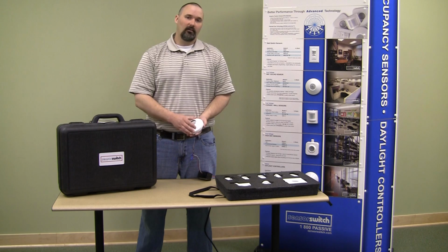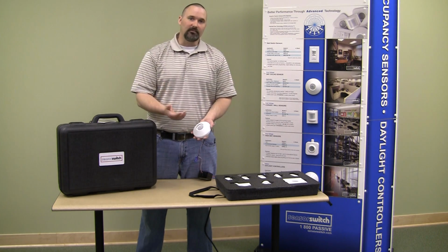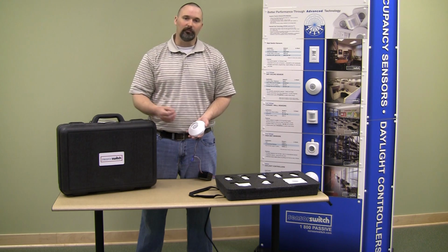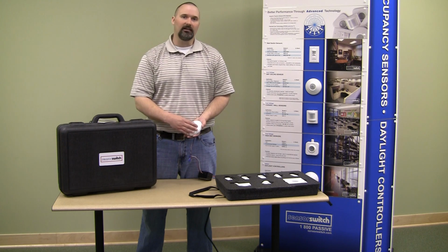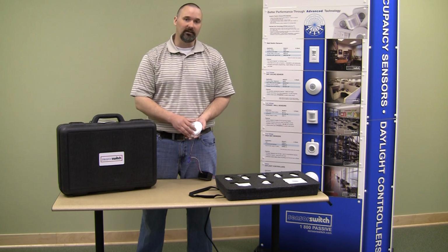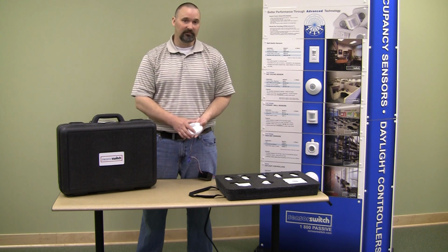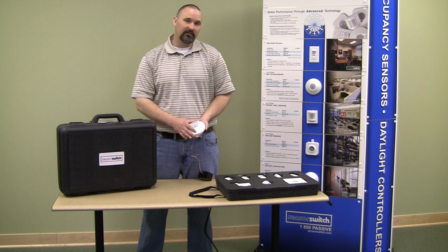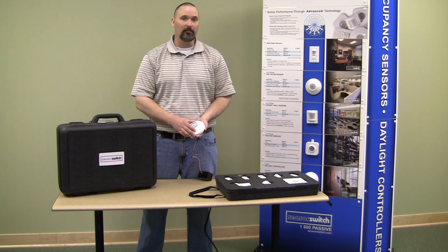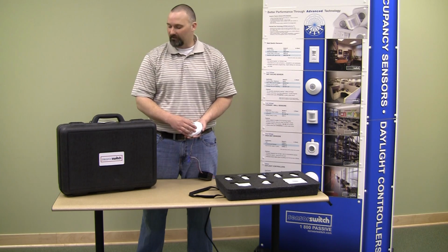space. The way that microphone operates is that first the sensor has to see you. At that point, we turn on that microphone. Once the sensor detects vacancy, meaning that it hasn't seen you or heard you for a period of 10 minutes, that occupancy sensor will turn the lights off. When those lights turn off, we keep that microphone on for an additional 10 seconds. After that 10 seconds has expired, we turn that microphone off, and the sensor has to see you once again before we'll activate that occupancy sensor and turn on those lights.